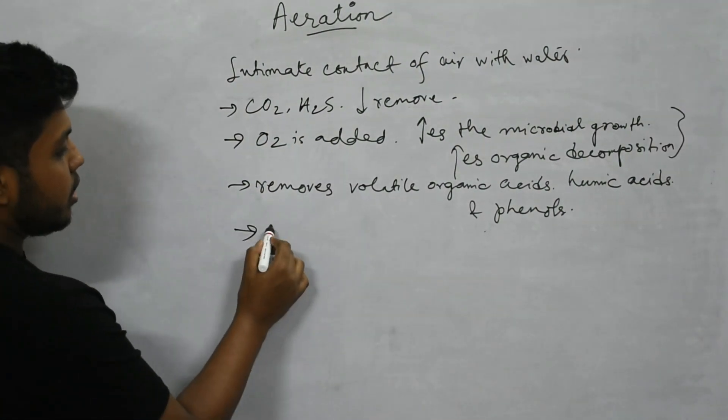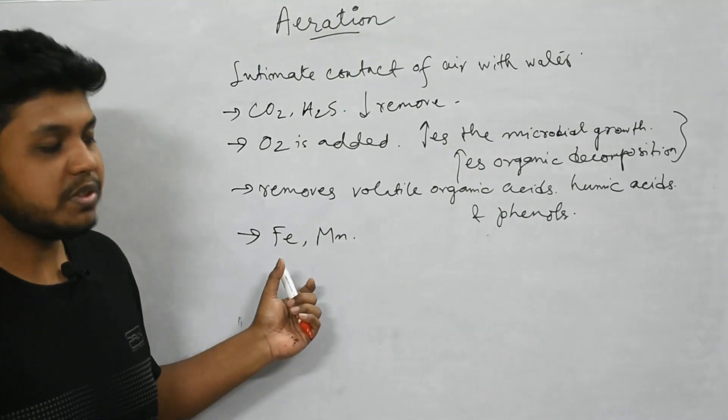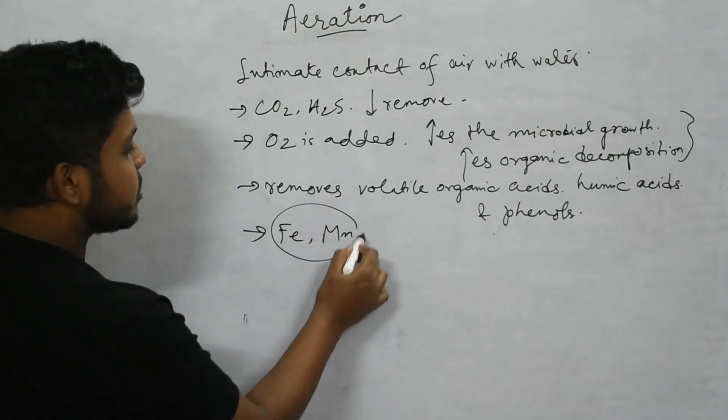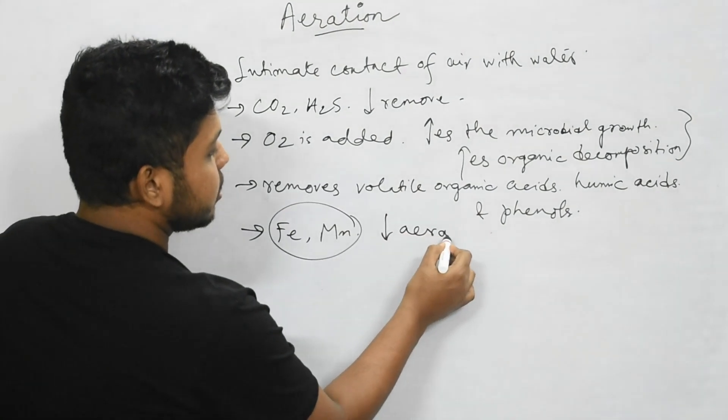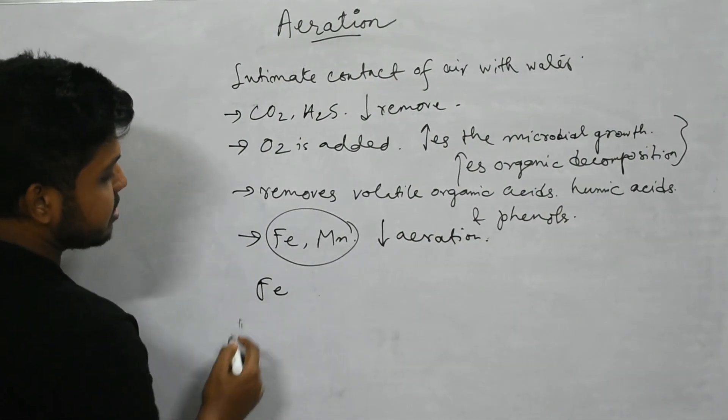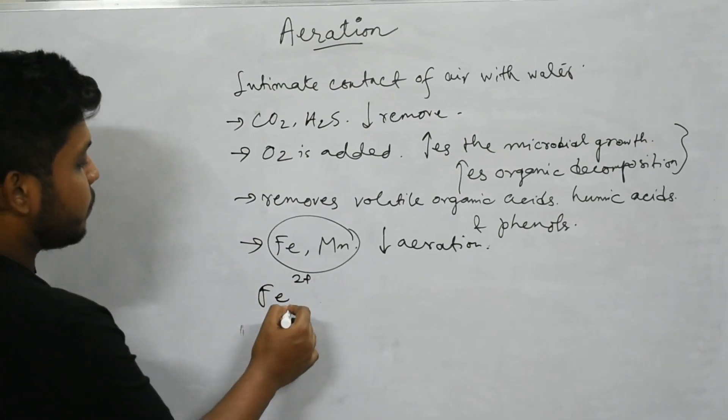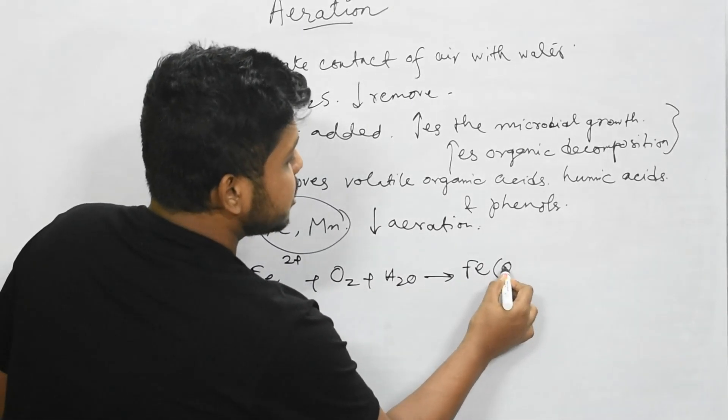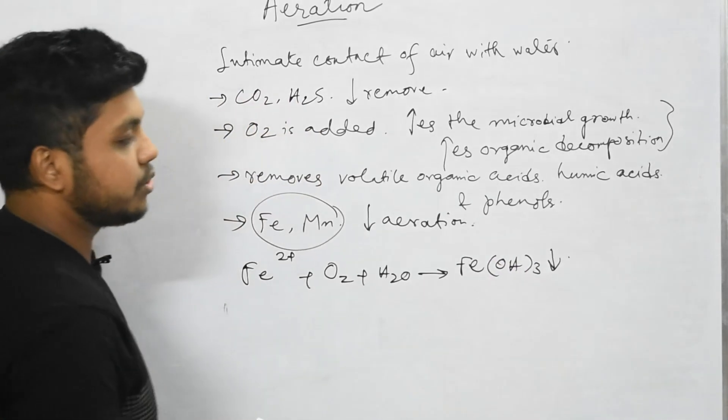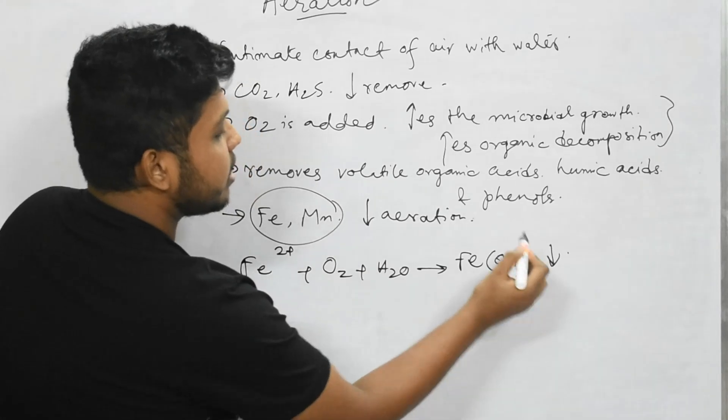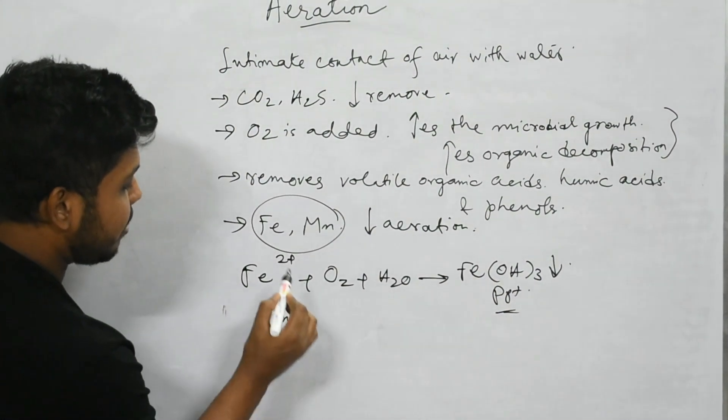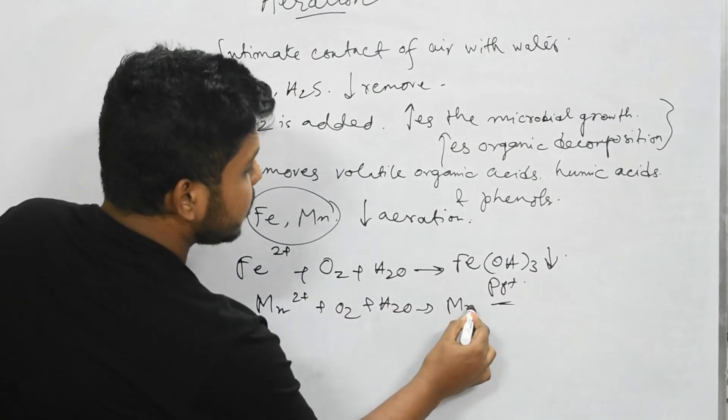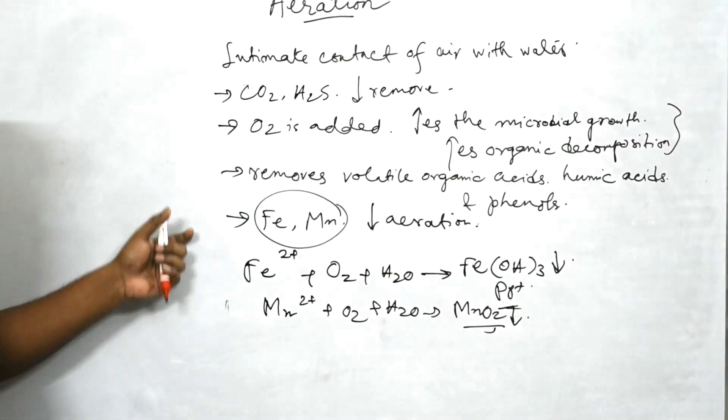Iron and manganese, the presence of these minerals is frequent in groundwater. Removal of these two minerals is possible by aeration. Fe is present in Fe2+ form which is a dissolved form which in contact of oxygen and water gets precipitated as Fe(OH)3. This precipitation gets removed as sludge. Again, Mn2+ in presence of oxygen and water precipitates as manganese dioxide. In this process the water can be purified through this aeration process.